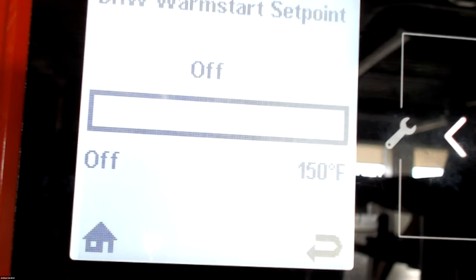So, you know, most cases we go in, say if a customer has a tank type water heater, they're used to getting that hot water instantly. But we switch over to one of these systems, we have to communicate with that homeowner that, hey, look, we're going to be much more efficient in our domestic and we're not going to kick on and keep the tank hot. We're only going to kick on if there's a call. So if you don't run your domestic and you're gone for a week, it doesn't call for a week.